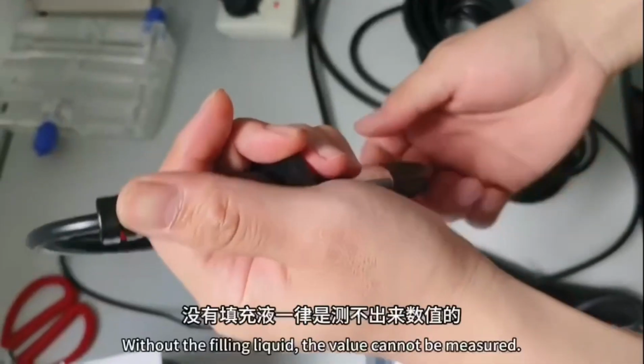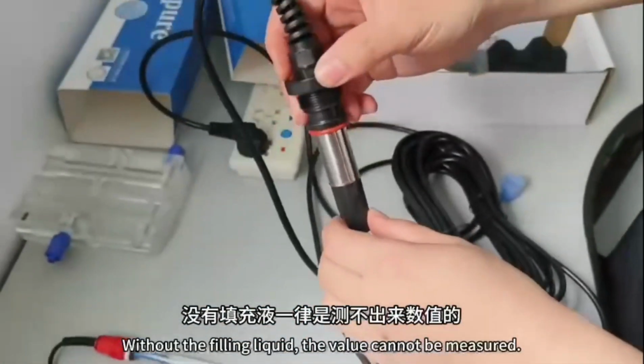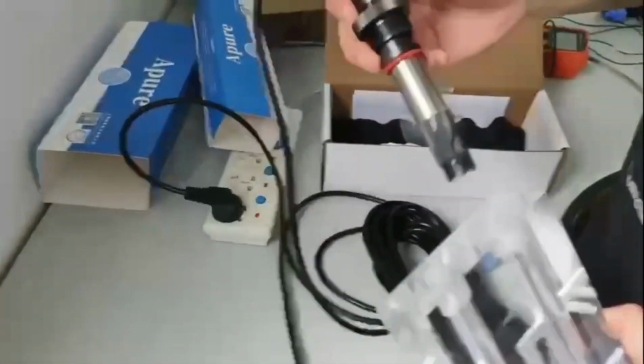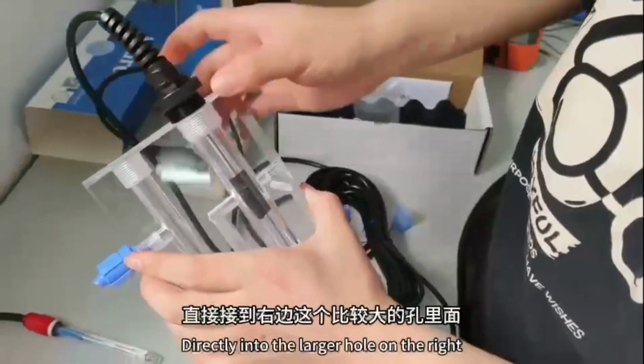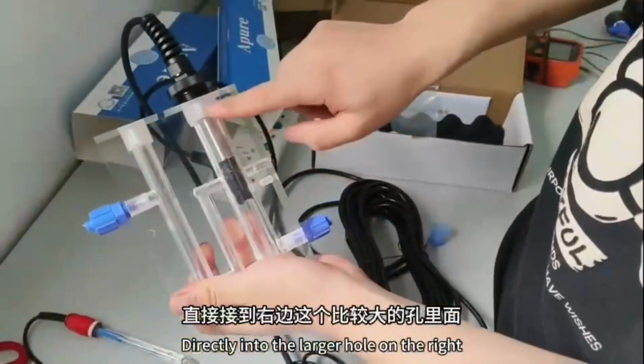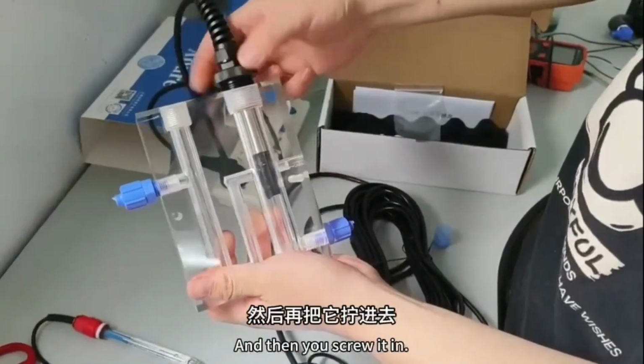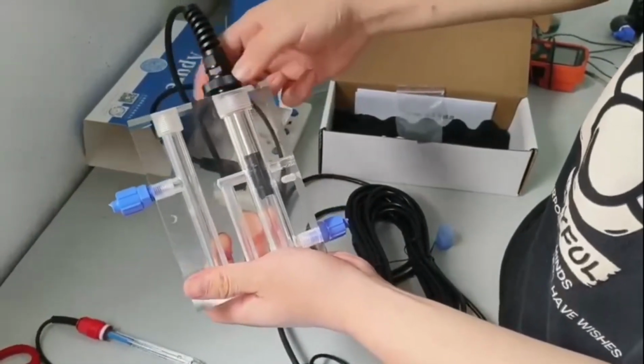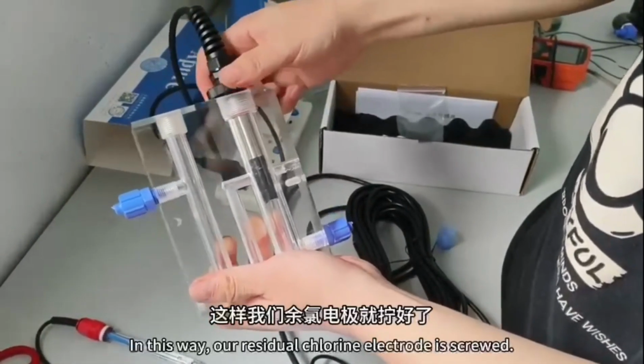This needs to be checked. Without the filling liquid, the residual chlorine cannot be measured. After screwing it, you can connect the residual chlorine probe directly into the larger hole on the right, and then screw it in again. In this way, our residual chlorine electrode is screwed in.